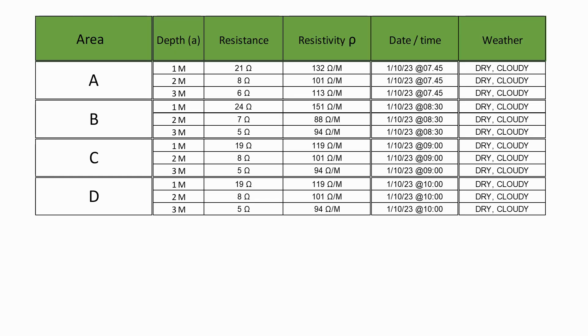Here are the results that we found. As you can see, for each result, we record the date, the time, and the weather, as whether or not it's raining when the measurement is taken can be quite important, as it will affect the soil resistivity value.